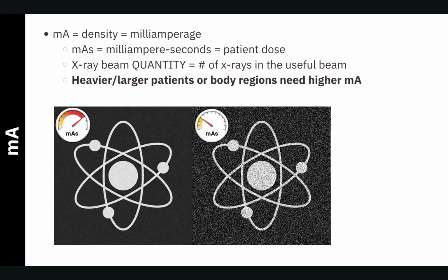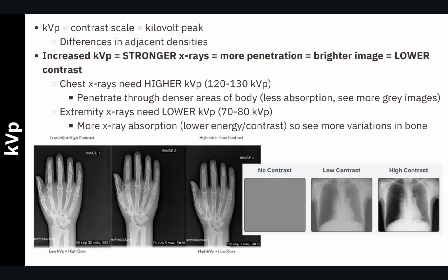So this image on the bottom here helps depict that if you use more MA, meaning you're giving way more radiation, you're going to get a clearer image. So it's always a balance of you want a clear image, but you also don't want to give so much MA that now you are giving an unnecessary amount of radiation. So it's always that balance of getting a good image, but also trying to reduce the amount of radiation. So again, that comes back to that concept of ALARA that I talked about earlier, about trying to give the lowest reasonable amount.